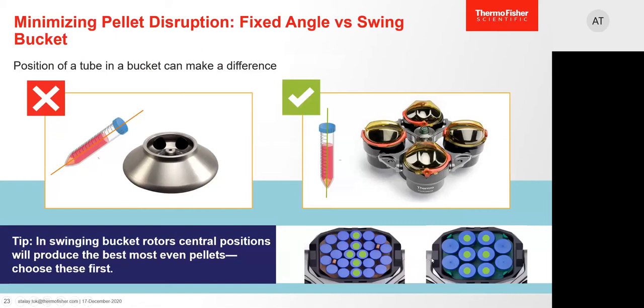Another tip: the choice of tube slot location also makes a difference. Different tube slots make different angles to the rotation axis. The central tubes are almost perfectly in line with the rotation axis, while neighboring tubes receive centrifugal force at a small angle, resulting in less even pelleting. To get the most even pellet, use the central slots — especially important when running a small number of tubes or when yield is very low.